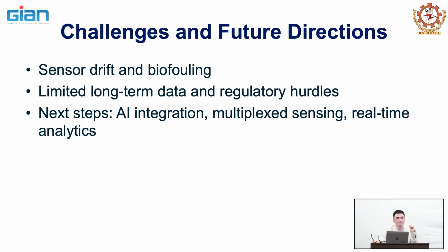You can address the problem of biofouling, number one, by bringing in a membrane that is perm-selective, that is only selective to the glucose molecules and does not allow the proteins that are being produced by the body to cover the sensor surface. That's number one, right? Over time, it will go and cover the membrane, but none of them will reach the sensor surface. And what will happen, even if it covers the membrane, the amount of glucose that will diffuse through the membrane onto the sensor surface will go down. So there's no way you can fight it, right? The body is definitely going to win.